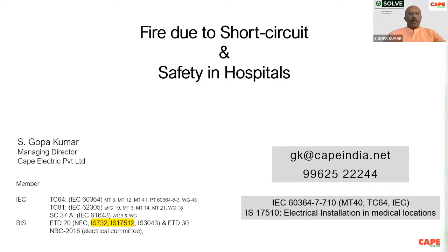The hospital safety worldwide, the mandatory rules of hospital safety has been made in the IEC standard 60364, part 7710. It's actually a part of the IEC standard called as 60364, electrical safety. Worldwide, across the globe, this standard has been adopted in Americas, in Europe, or in all the developed nations. So in India, the same standard has been adopted as IS 17510. It's not 512. I'm sorry, I made a small mistake while typing a little bit faster. Electrical installation, medical locations. This standard has been published in 2021. And this standard is in IEC, it's made by the MT40. MT stands for maintenance team, MT40 of TC64, where I'm a member.